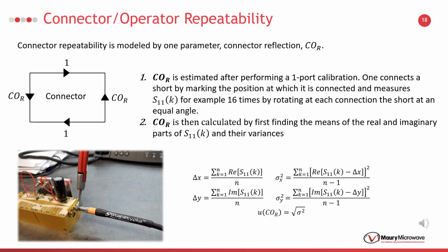Connector repeatability is modeled by one parameter, connector reflection, or C_oR. C_oR is estimated after performing a one-port calibration. A short termination is used for the S11 measurement. The S11 of the short is measured several times. Between each measurement, we disconnect and reconnect the connector, and each time we disconnect it, we rotate the termination by a fixed amount before connecting it back again. Standard deviation of the real and imaginary parts of the measured data is used as the uncertainty parameter of connector repeatability.